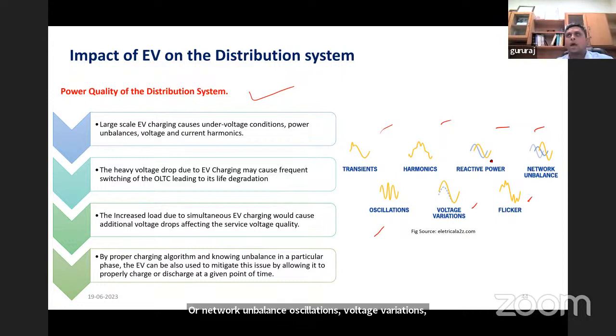Let me give you a narrative. If there are multiple EVs collectively taken at a specific bus and charging power from this bus, what happens? Naturally the voltage would drop, and there is an on-load tap-changing transformer connected to this bus, whose responsibility is to maintain the voltage at that specific bus at 1 per unit.